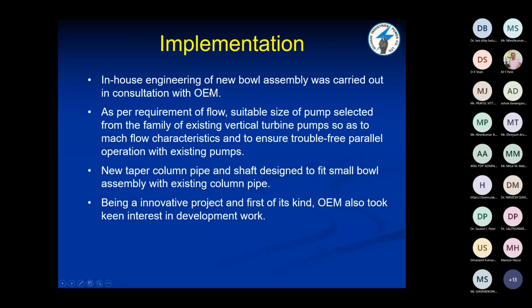Now, in-house engineering of the new bowl assembly was carried out in consultation with the OEM. The OEM was Jyoti make pumps. So we consulted the engineer of Jyoti, and as per the requirement of flow, a suitable size of pump was selected to match the flow characteristics of the existing water pump and to ensure trouble-free parallel operation. The new taper column pipe, we have taken from Jyoti, that is the OEM. I will show you the figure of that also.